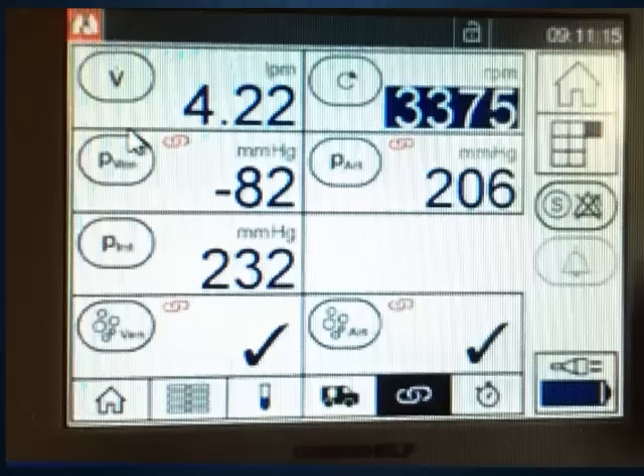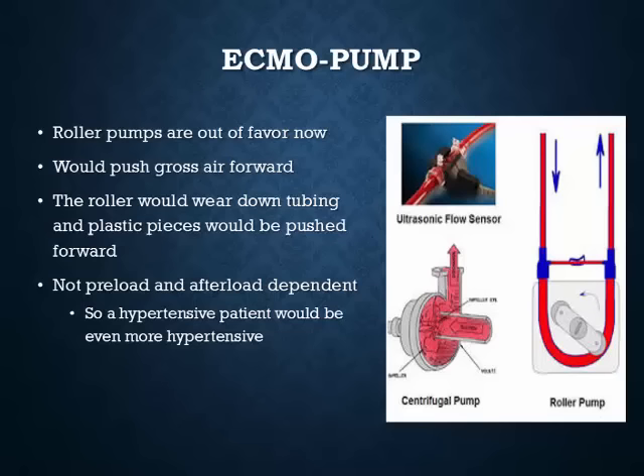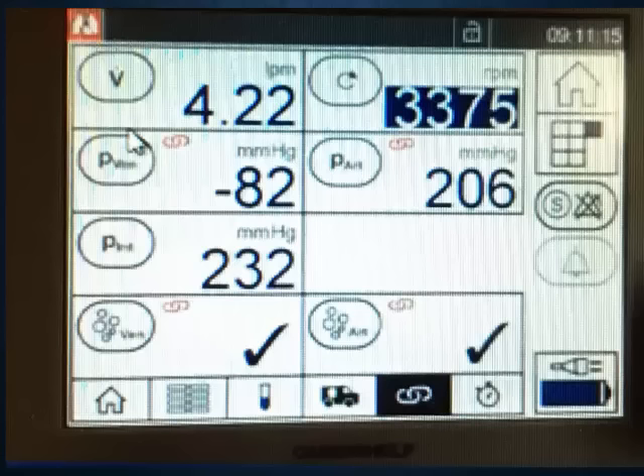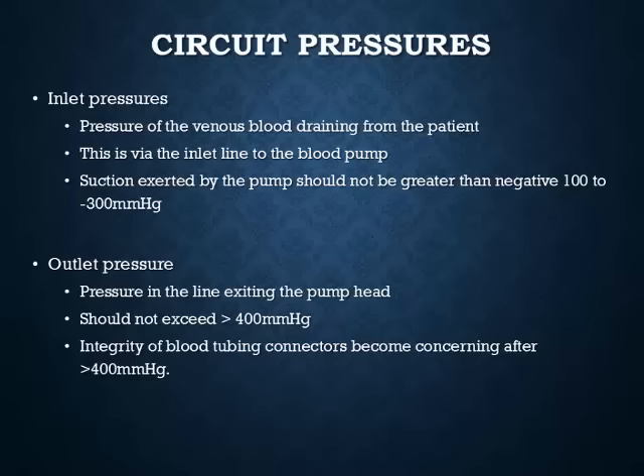On a typical console, you'll see cardiac output, RPM, pre-oxygenator and post-oxygenator pressures, and the inlet pressure. The more recent machines, including those at Henry Ford, have detectors for bubbles — usually macro bubbles, not micro bubbles. Macro bubbles can actually be seen in the tubing itself. Obviously, you don't want any air bubbles going toward the patient.